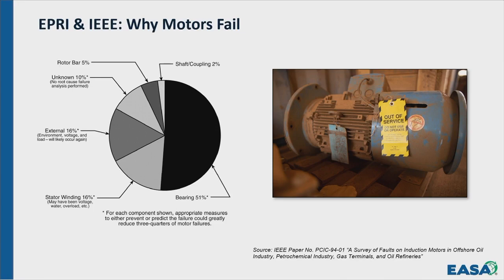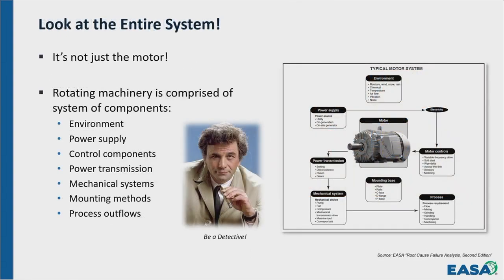But there's categories of failures. Look at those. Use the EASA guidance and hone in on the root cause, the problem, and then ask yourself questions. And oftentimes this happens a lot, especially if you say, okay, I had a motor fail. So you're focused on the motor. Why did it fail? Well, you have to step back too and look at all the conditions. There's many external factors that can be involved instead of just the motor.